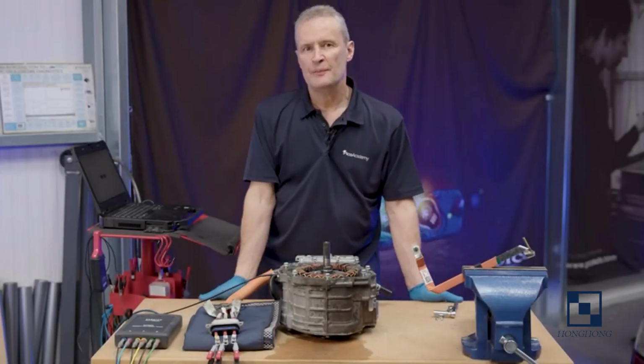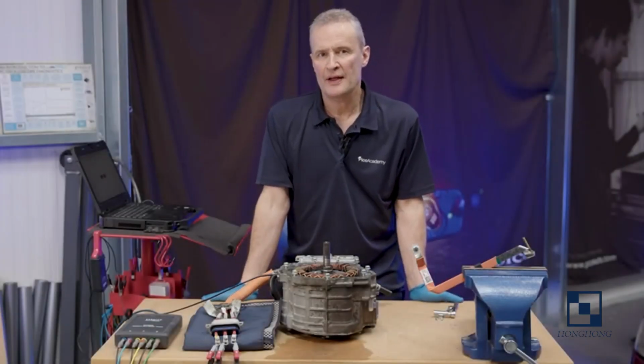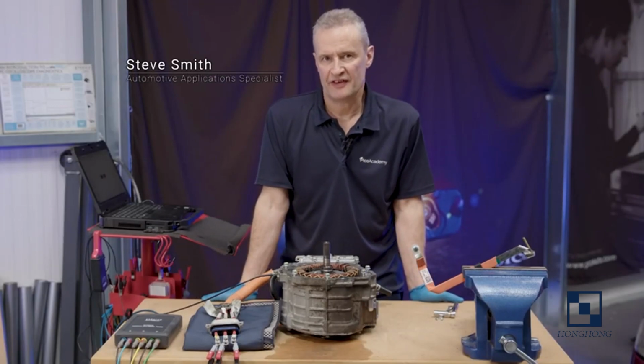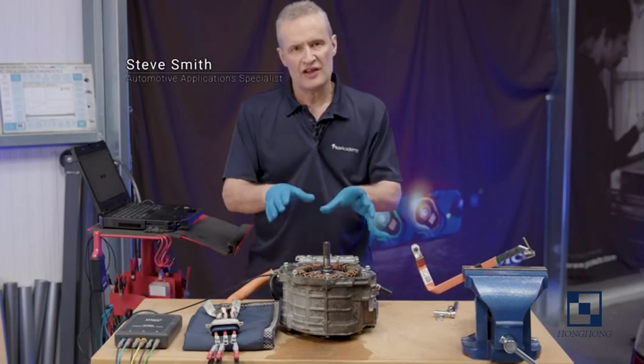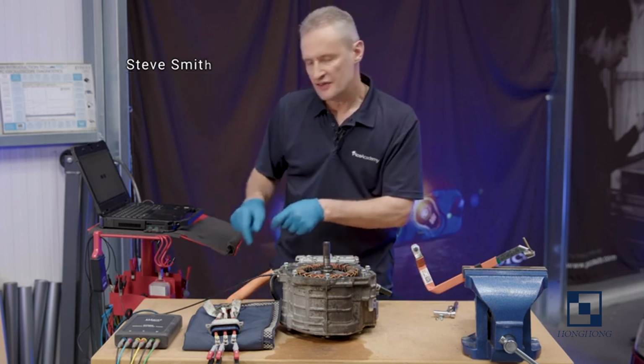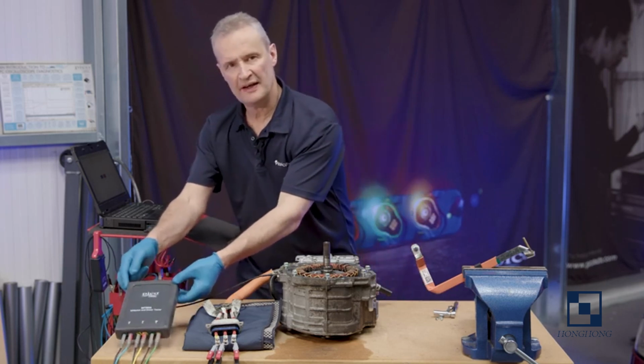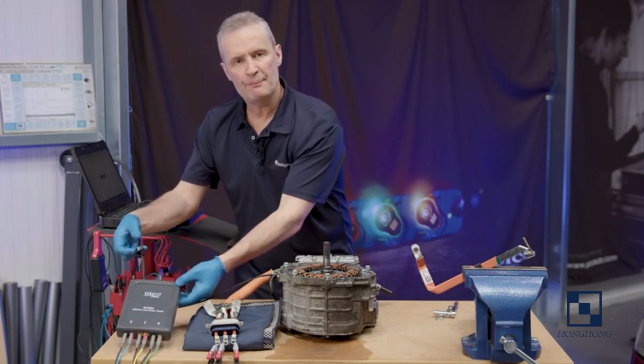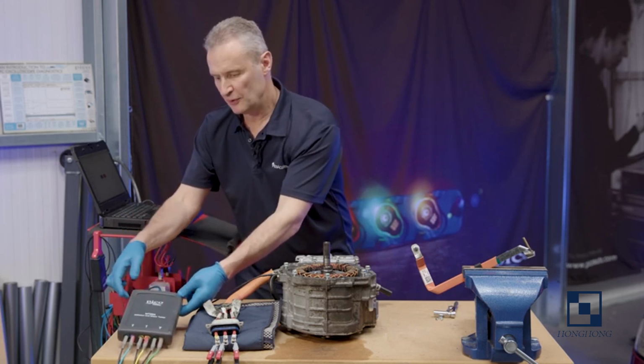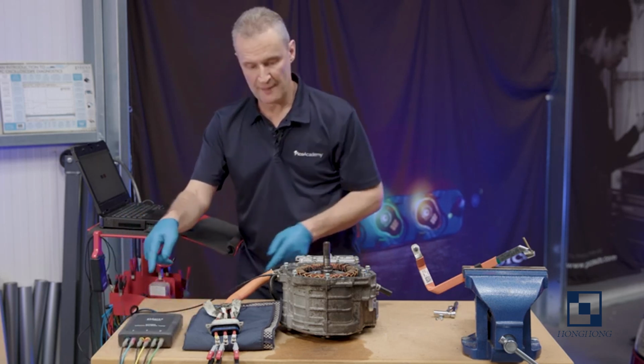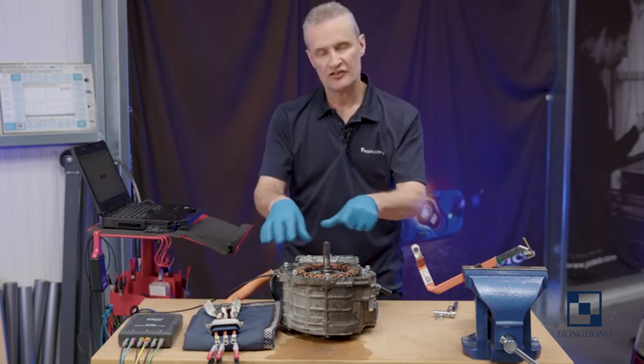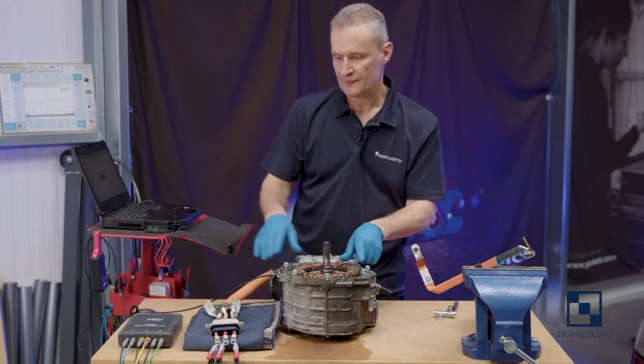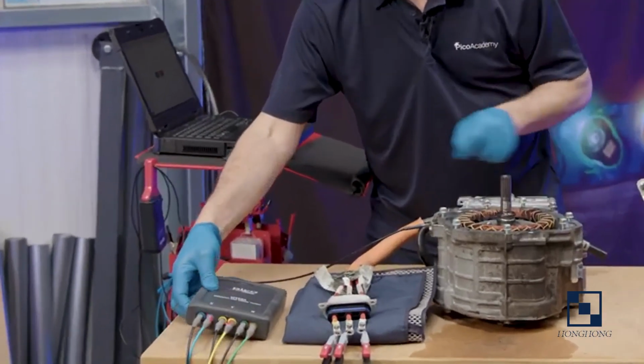Milliohm testing using the Pico MT03A milliohm and motor tester. We're going to look at phase winding resistance using this tool, with USB connectivity. A 3.5mm jack plug into the back of the unit will measure temperature, so we'll get our temperature probe as close to the motor casing as we can. It uses the 4-wire Kelvin method.